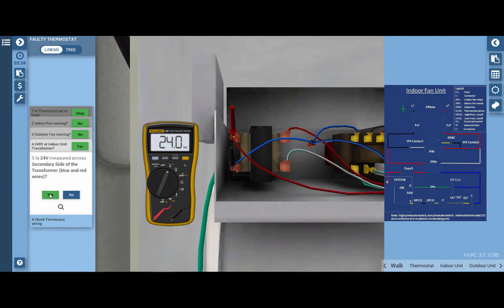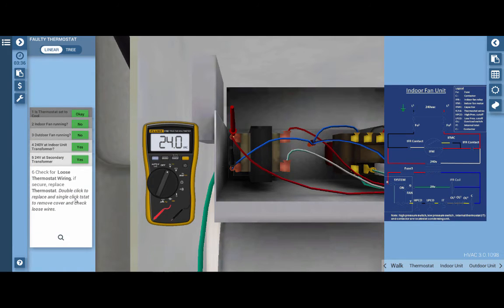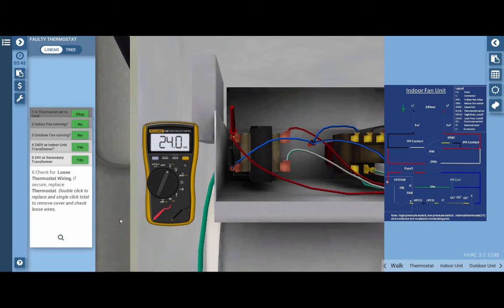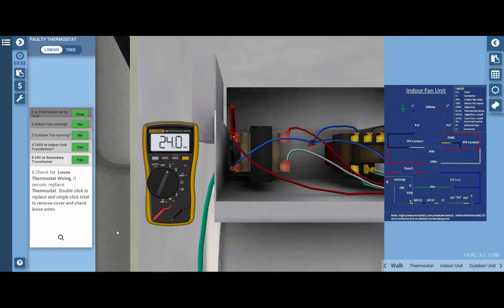We do have 24 volts, so we're going to click yes. And we want to go to the thermostat and we want to check the wiring first. But at this point, there's no other component that could be at fault. We don't have power coming out of that thermostat because neither of these electrical loads are operational. So let's go to the thermostat. And again, I'll use the magnifying glass to do this.